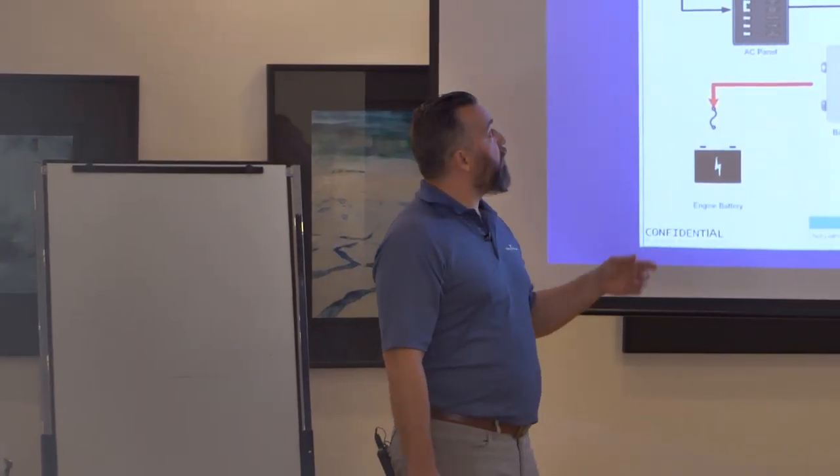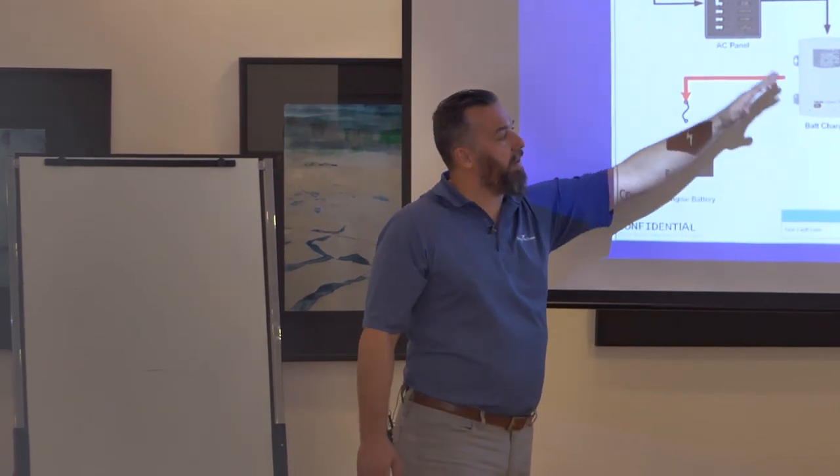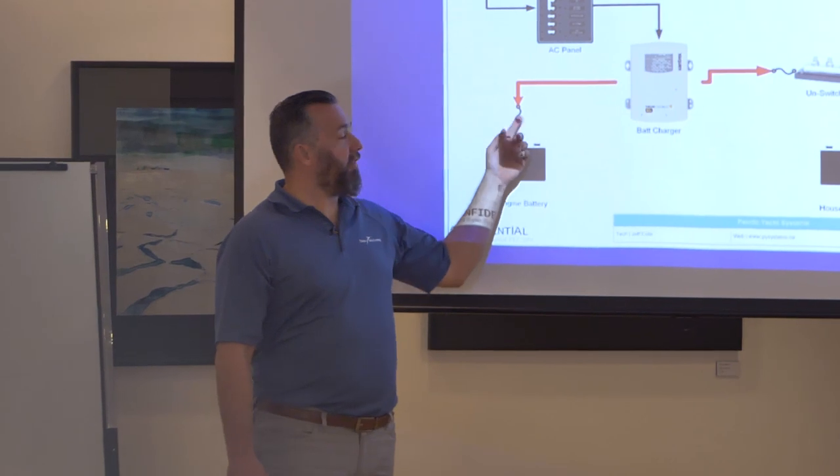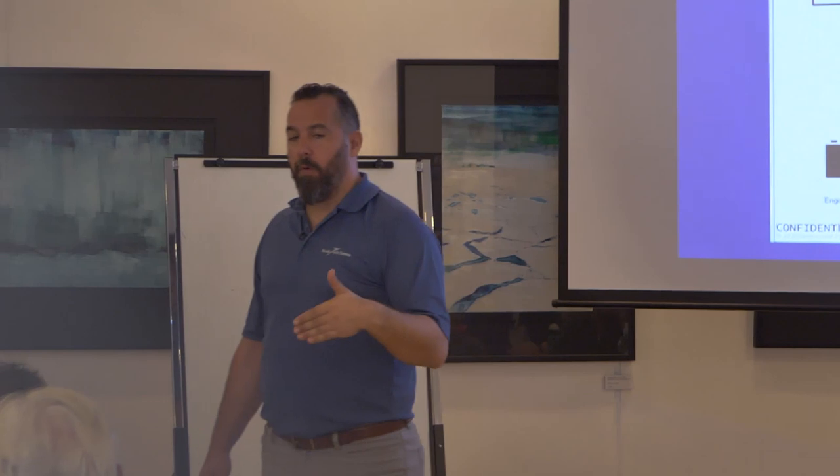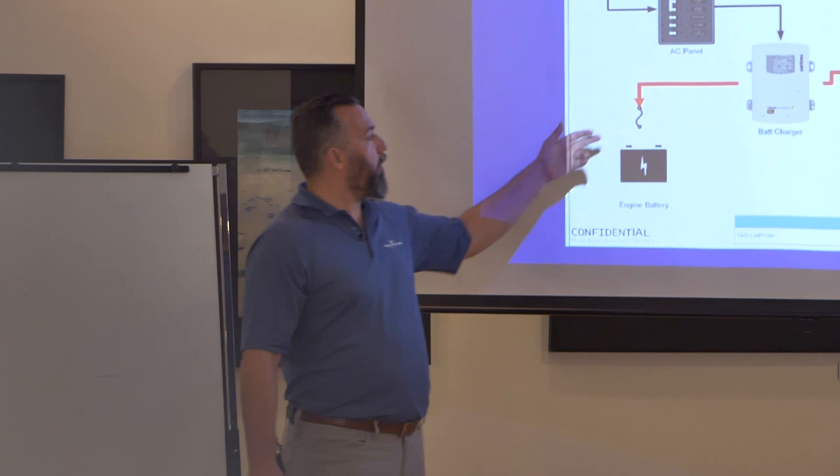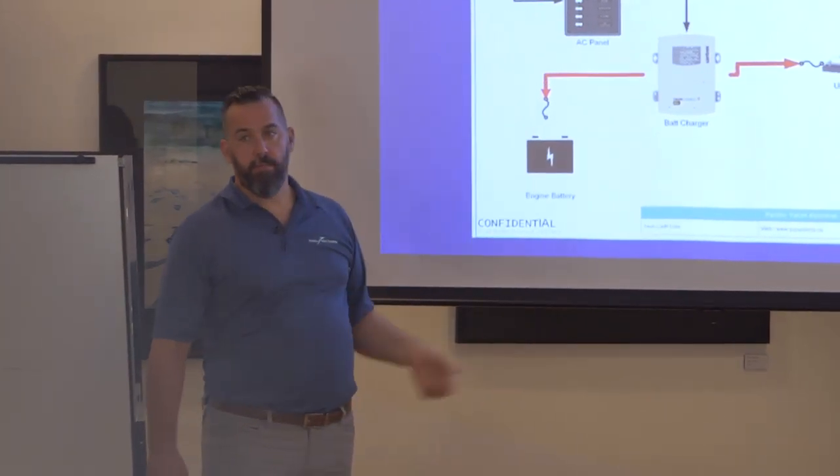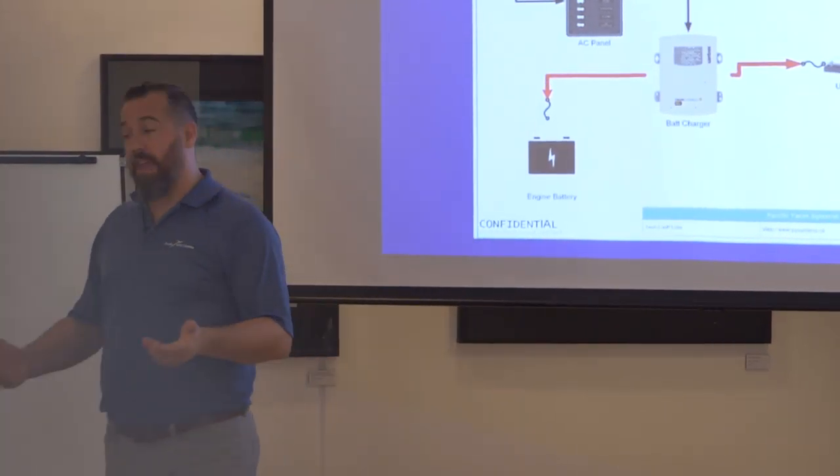Or, that your charger's badly installed, and it's on a switch, and I've seen that where charger outputs are switched, never should be, black and white, and the switch near the battery is off, and you have to have the battery switch on for the charger to be connected to the battery. Basically, that's how you troubleshoot a charger. It's not that hard, but you start from the source, and you work your way down. It is definitely possible that your fuse will be blown. It's possible. A lot of people will put a 40 amp fuse on a 40 amp charger, thinking that a charger is a load. It is not a load. A charger is a charger.